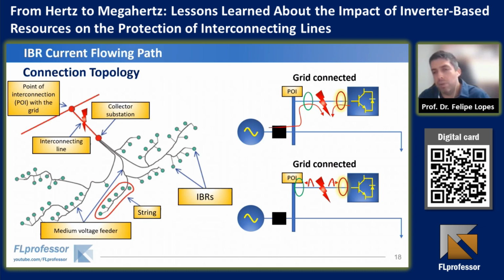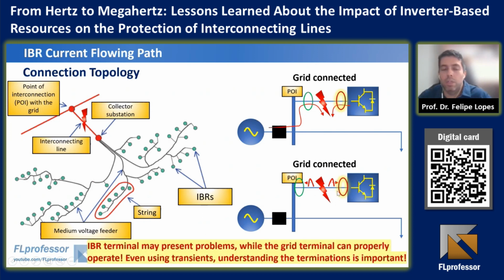Because if I want to protect this line, considering traveling waves, I have to measure traveling waves on the IBR side, and also on the grid side. But these terminations have different characteristics. So the IBR terminal may present problems, while the grid terminal can properly operate. But even using transients, and we know that transients do not depend on the IBR controls, understanding the termination is very important.